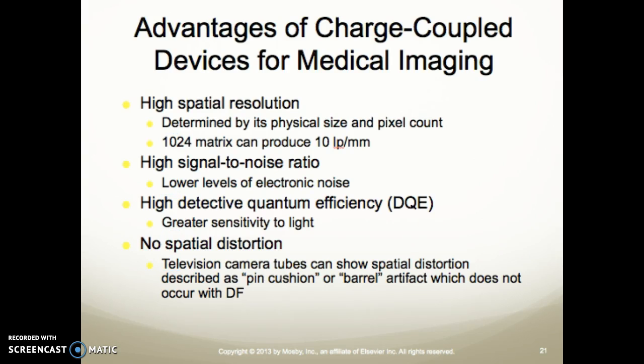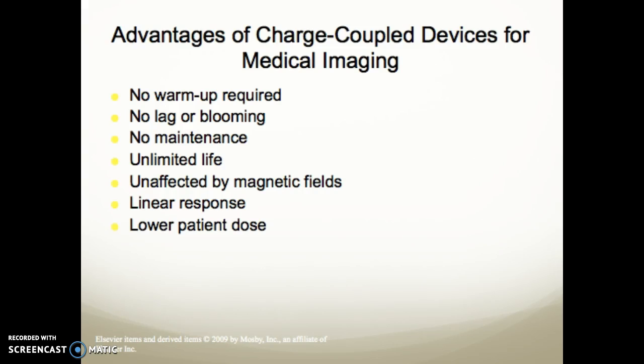Advantages of charge-coupled devices include: high spatial resolution determined by physical size and pixel count — a 1024 matrix can produce 10 line pairs per millimeter; high signal-to-noise ratio with low levels of electronic noise; high DQE with greater sensitivity to light; and no spatial distortion, unlike TV camera tubes which can show pincushion or barrel distortion. There is also no warm-up required, no lag or blooming, no maintenance, unlimited life, and the CCD is unaffected by magnetic fields, which is important when using magnetic-tipped catheters in IR or cath lab.